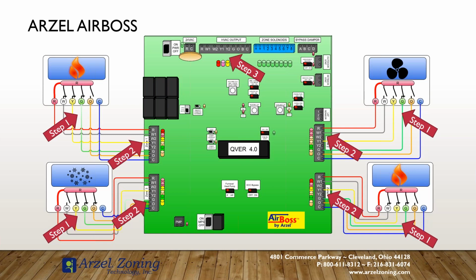So G, Y, and W, if you notice, so your question is zone 1 thermostat has closed G, Y, W, is it in heating or cooling mode? But if you notice at zone 3, it has Y, G, and O closed. So if you remember back to the thermostats, O is always a call for cooling when you have a heat pump.